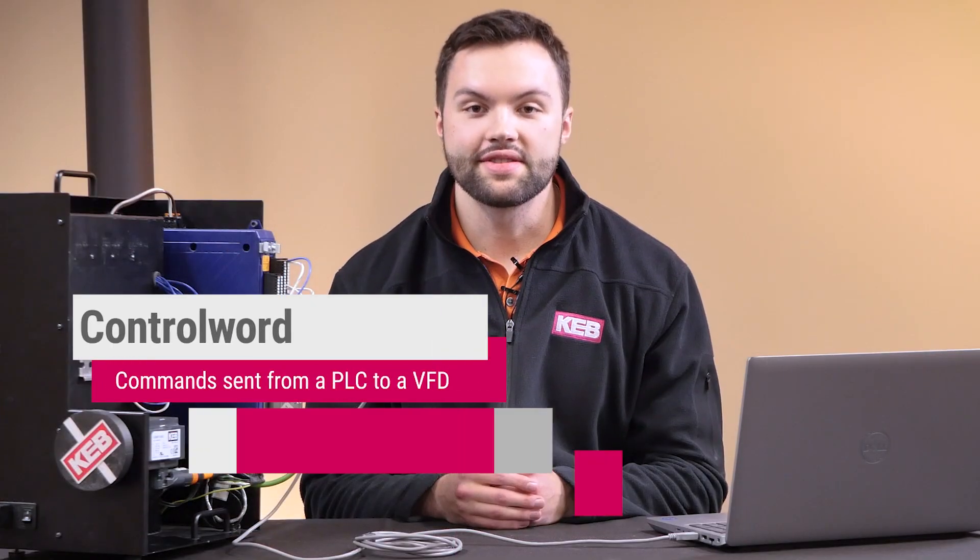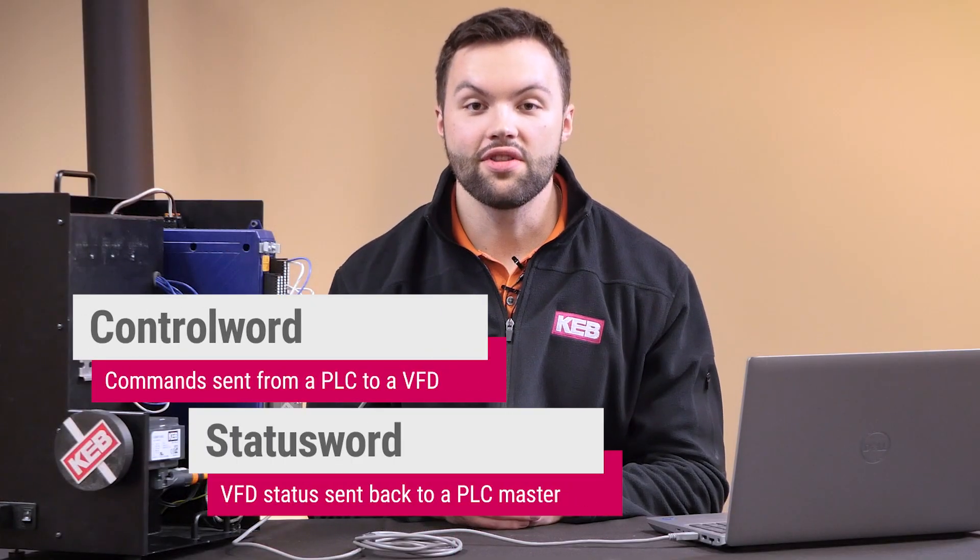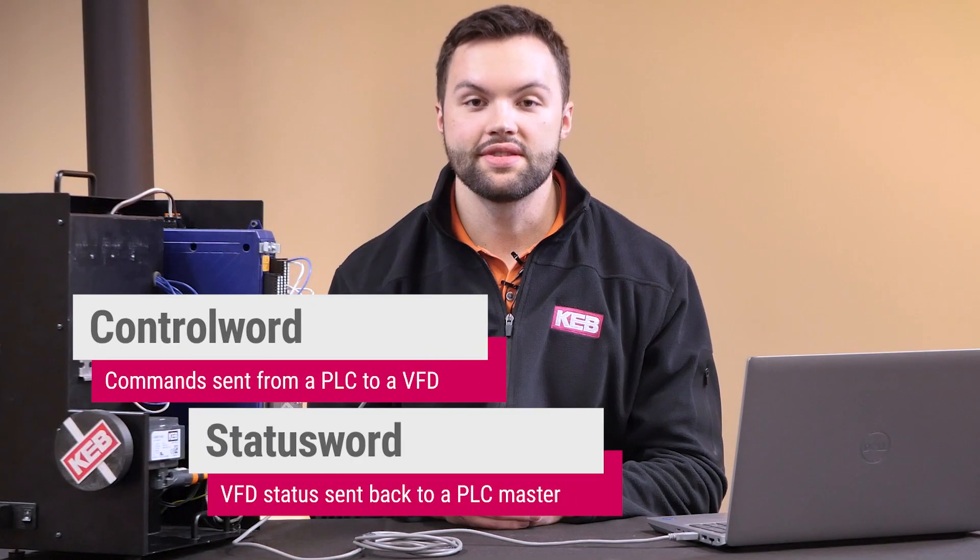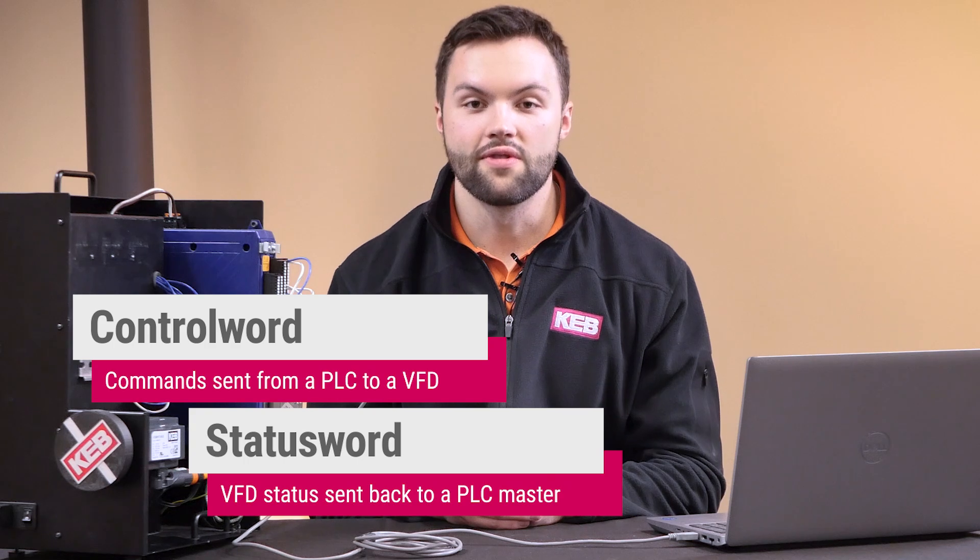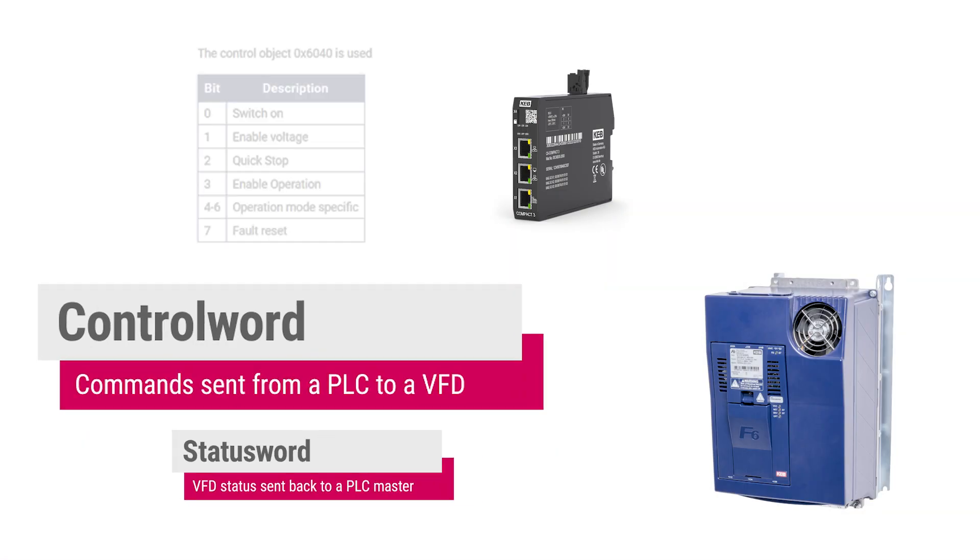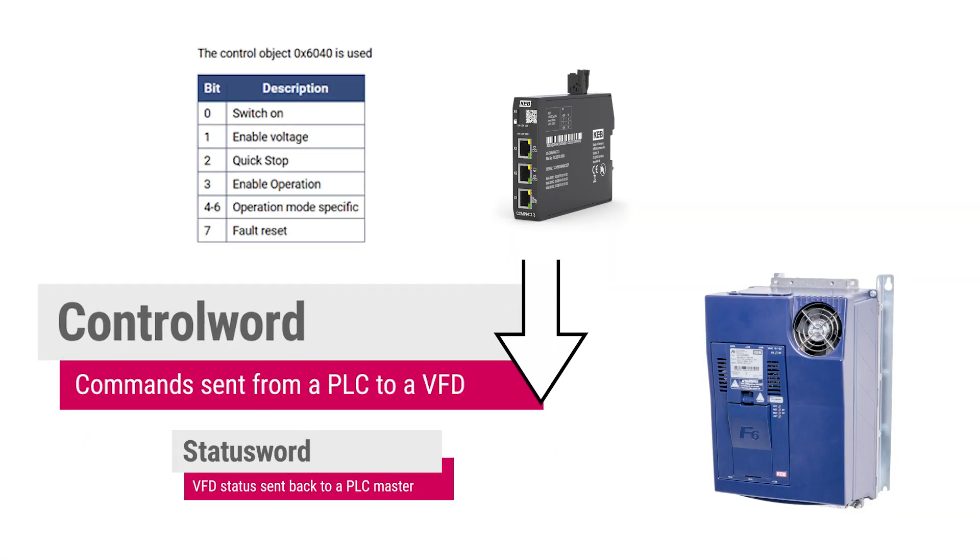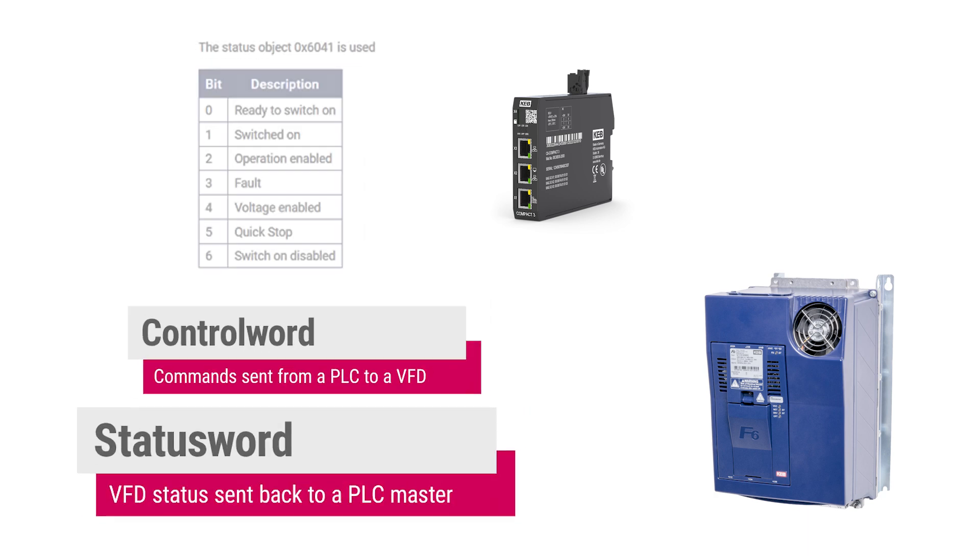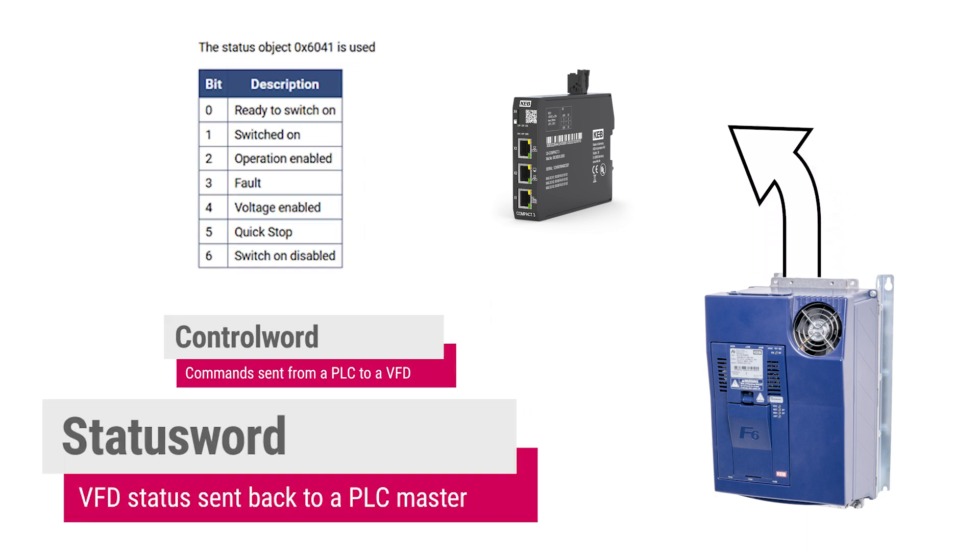The control word and the status word are heavily used in the CIA402 device profile. The control word is used to request state changes on the CIA402 state machine. The status word is the feedback used to get the state of the CIA402 state machine.